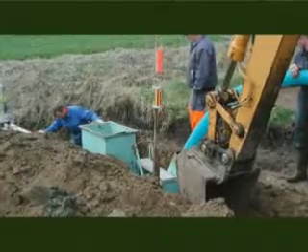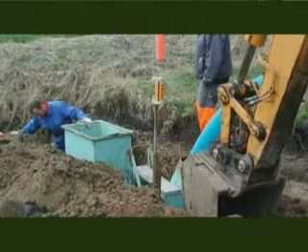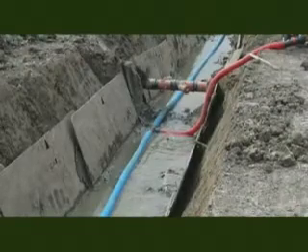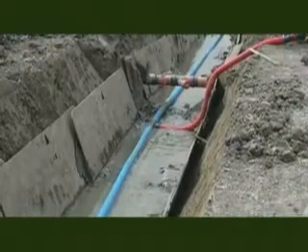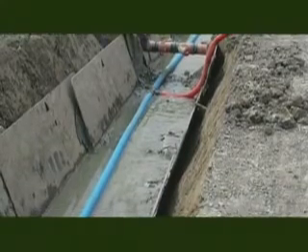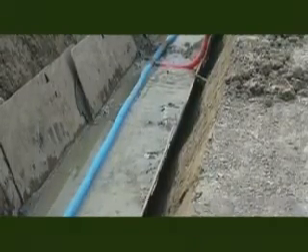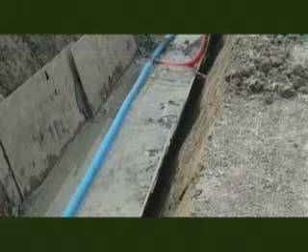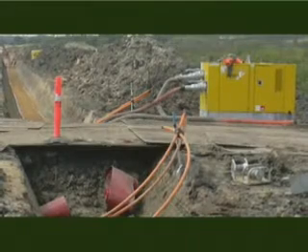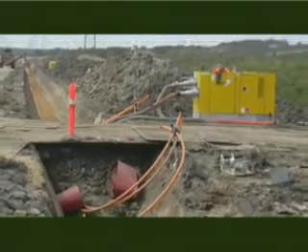A drainage pipe is ploughed into the cable route, deeper down than the final cable depth. This allows dewatering of the area during the establishment of the system. In some places, it's necessary to lay a drainage pipe on top of the cable so as not to create soft spots above the cables.